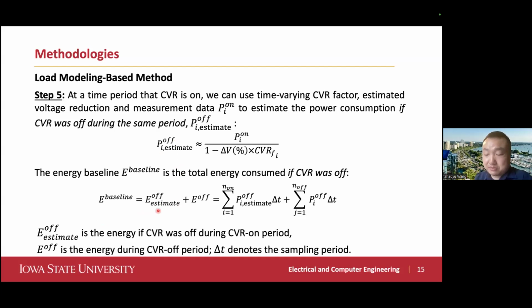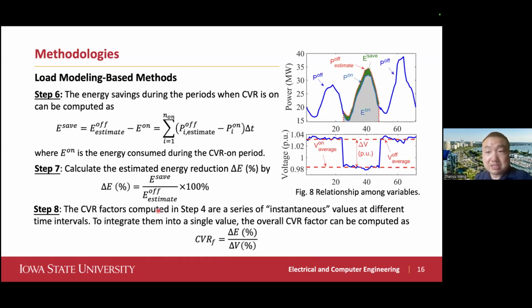Using this equation, I'll skip the details, but you can reconstruct this red dotted line, and the difference between the red line and the measured one will give you delta E. With delta E and delta V, you get just one single CVR factor. So basically you combine all the time-varying CVR factors into one single value, which you can then report to the regulation agency.